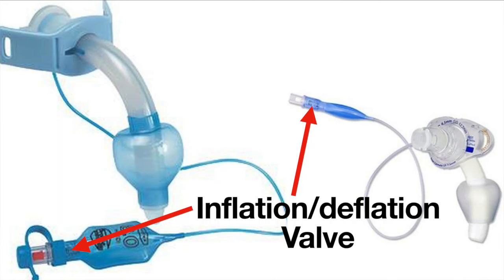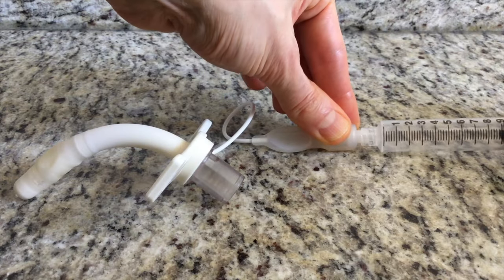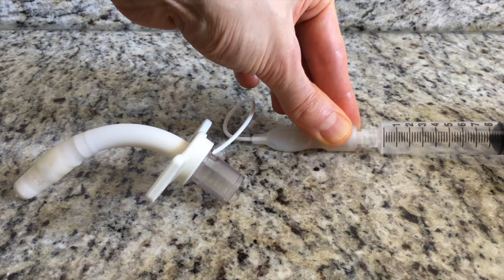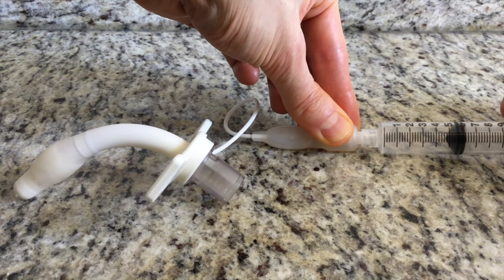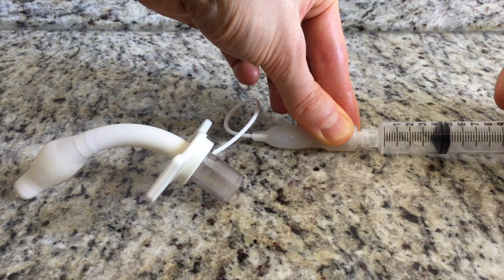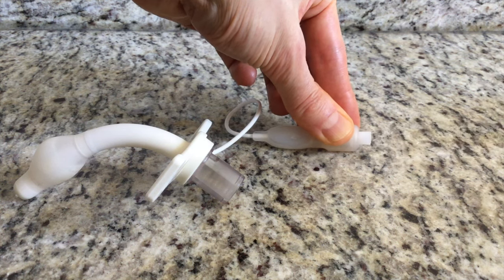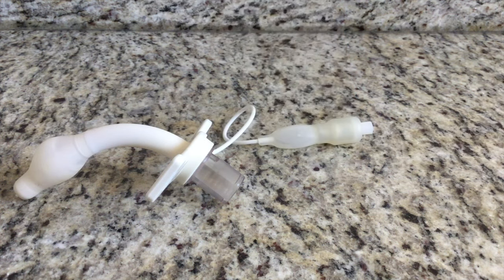At the end of the pilot line, there is a valve which controls the pressure inside the cuff on the tracheostomy tube. When the valve is pressed down, the cuff can be either inflated or deflated by using a syringe. When the valve is closed, the inflation line is sealed which prevents the cuff from being inflated or deflated.